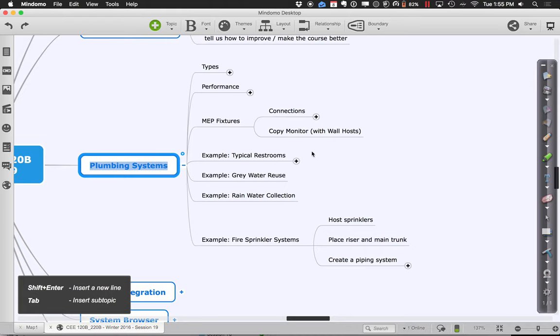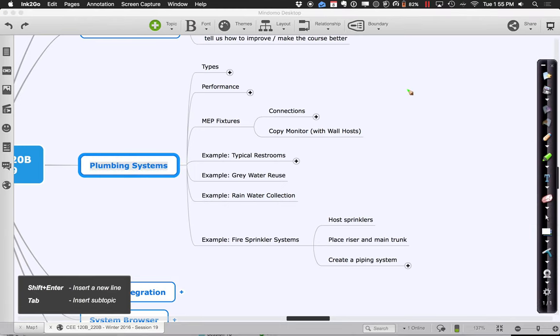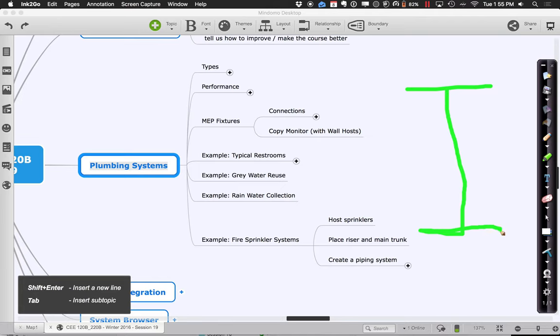The biggest concern with fire sprinkler systems is the height you specify for them, because you have to think about the level at which they're running versus your other pipes, your ductwork, and your structure. What often happens is since fire sprinkler pipes are relatively small relative to structure, they often run up within the structural layer. If you have open web joists or beams with penetrations through the flanges or web, you can have those penetrations since they're relatively small — as opposed to ductwork, which is so big it's really hard to cut an opening in a beam web without compromising it.